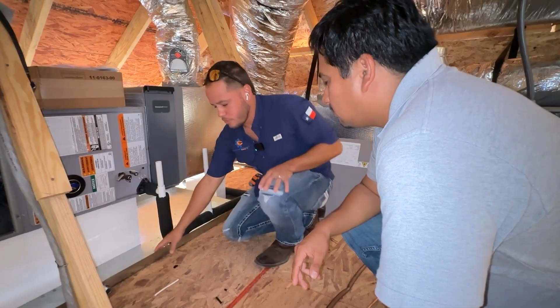And what's the point of the float switch? Basically, if the primary drain line gets clogged, the float switch, like the word says, floats. If the water pushes up the float, it's going to cut the power for the equipment. So we always like to go a step further, and that's why we use the secondary float switch in the drain pan. If for any reason this one's failed, the other one is going to cut the power as well. Essentially, if it fails, then there's actual water dripping. The water from the equipment is going to fall into the drain pan.